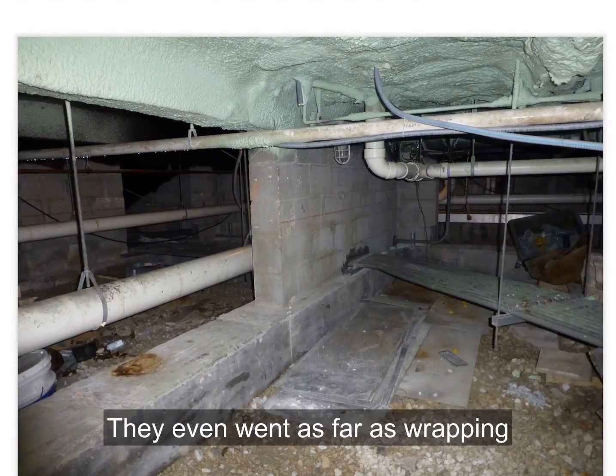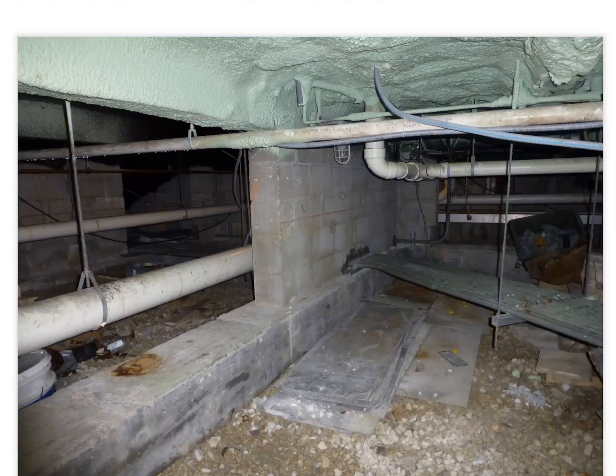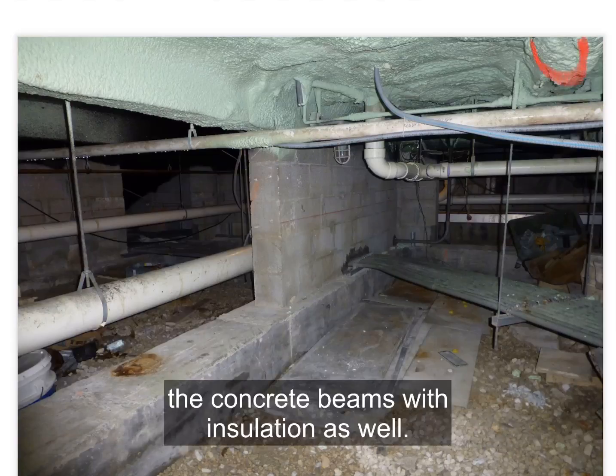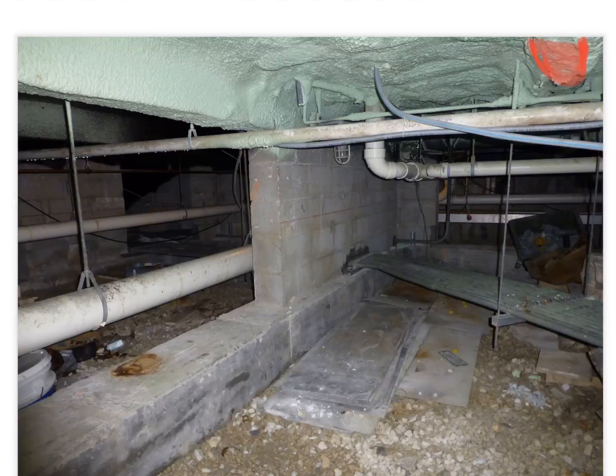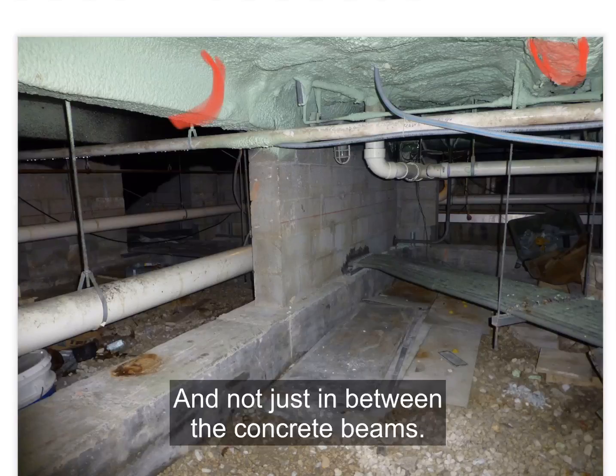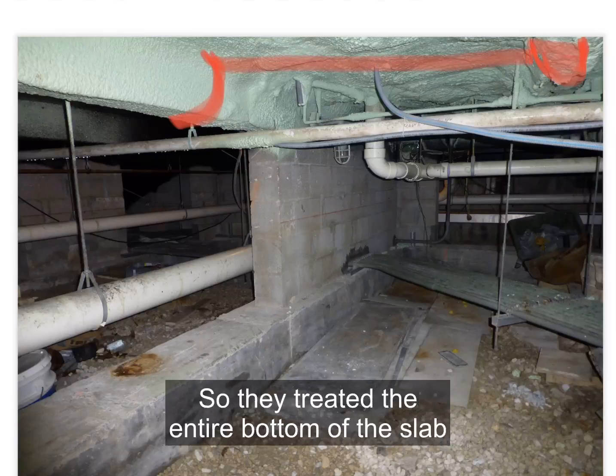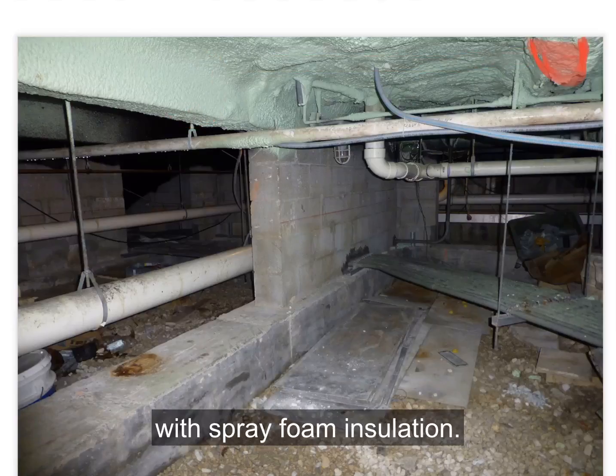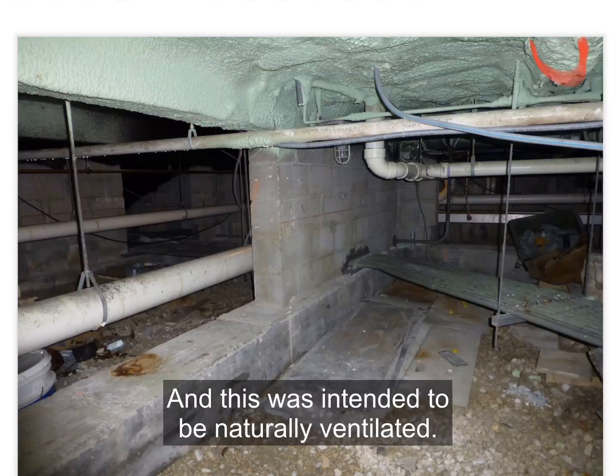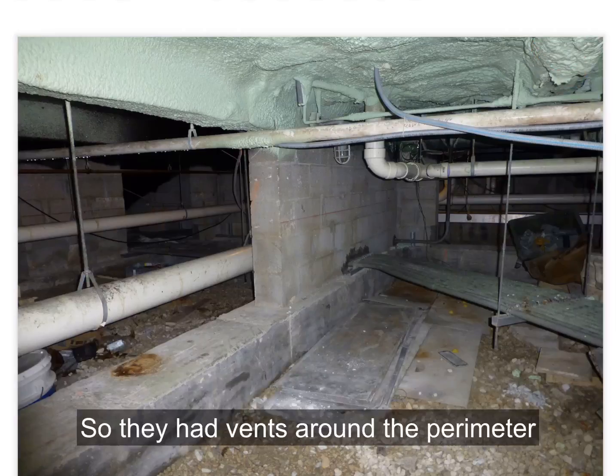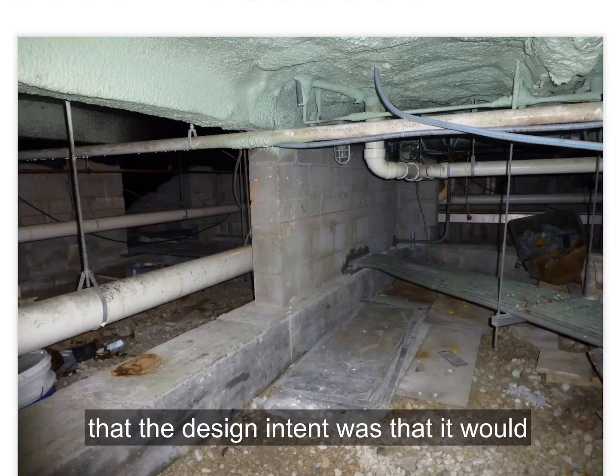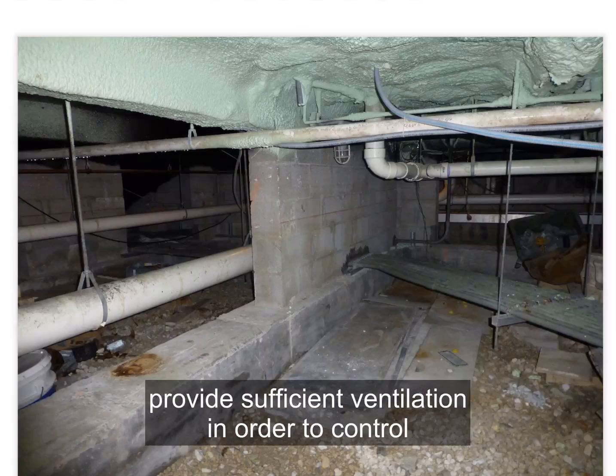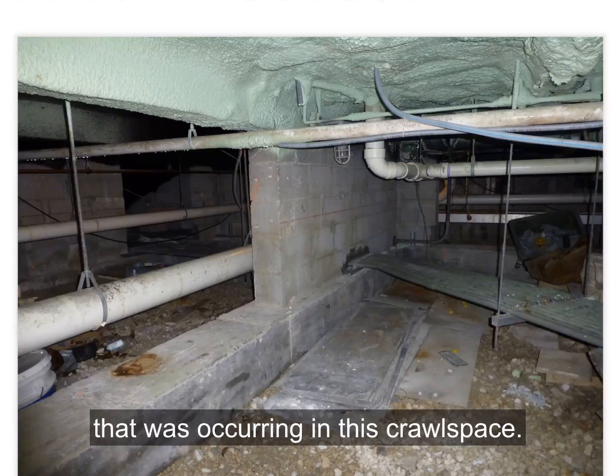They even went as far as wrapping the concrete beams with insulation as well, and not just in between the concrete beams. So they treated the entire bottom of the slab with spray foam insulation. And this was intended to be naturally ventilated. So they had vents around the perimeter, and the design intent was that it would provide sufficient ventilation in order to control any kind of moisture accumulation that was occurring in this crawl space.